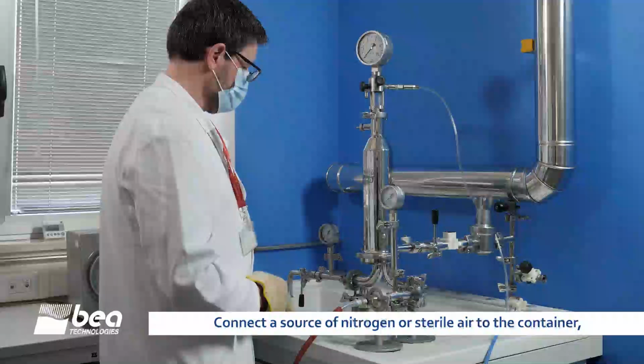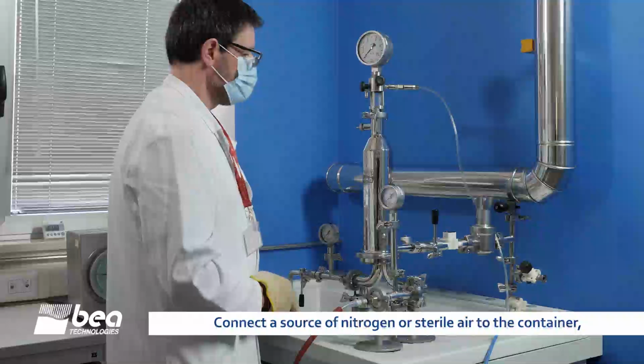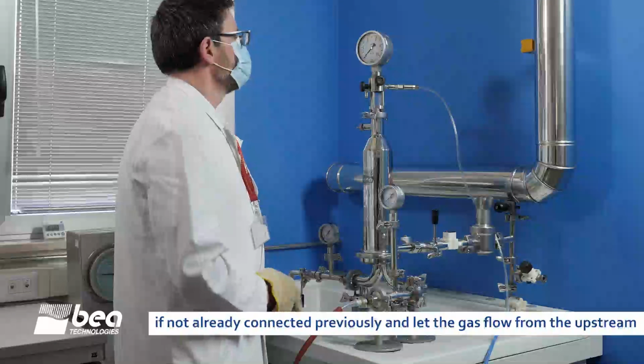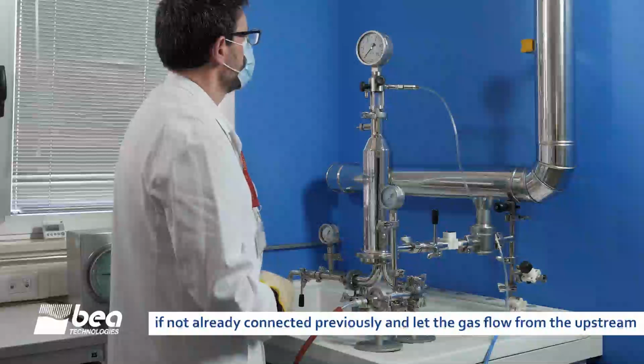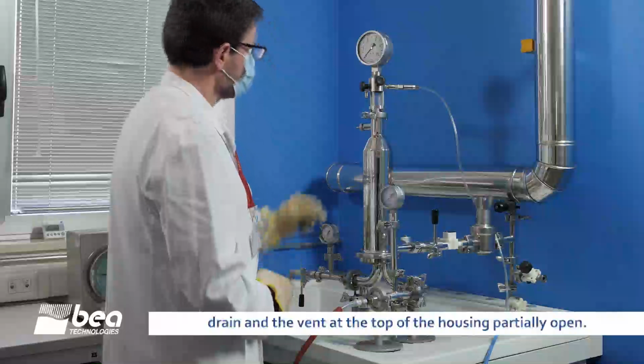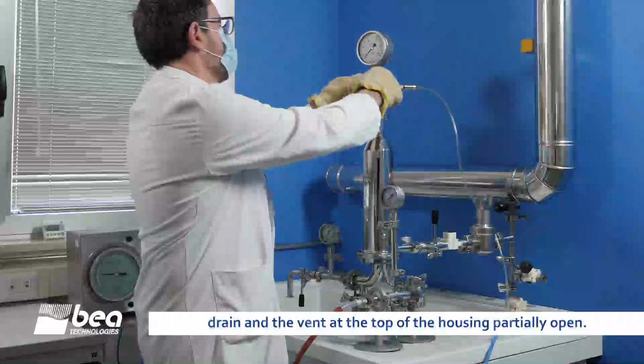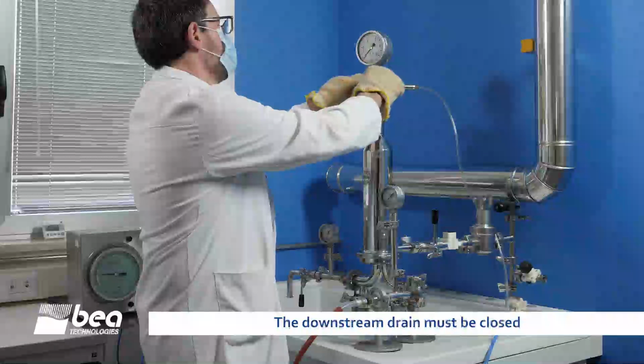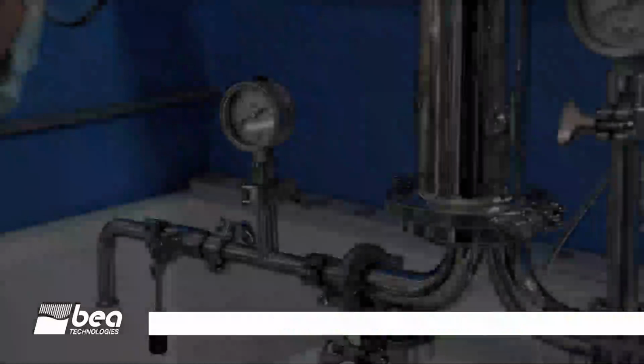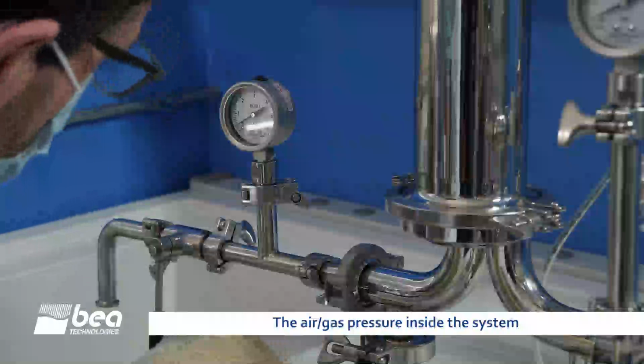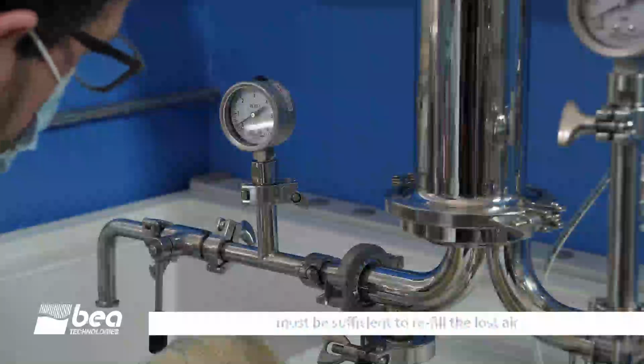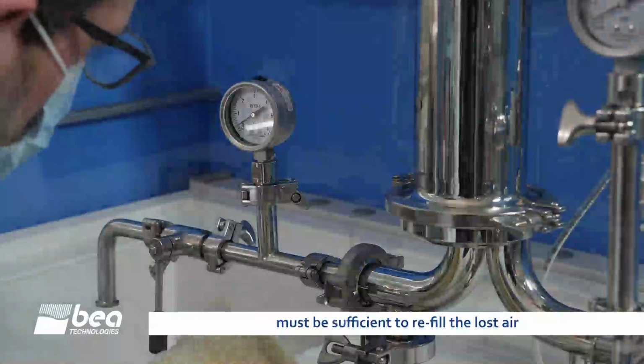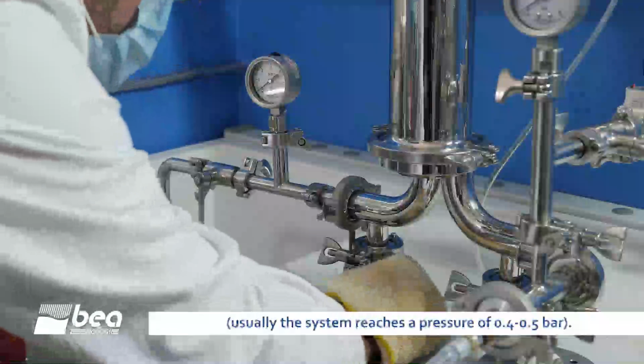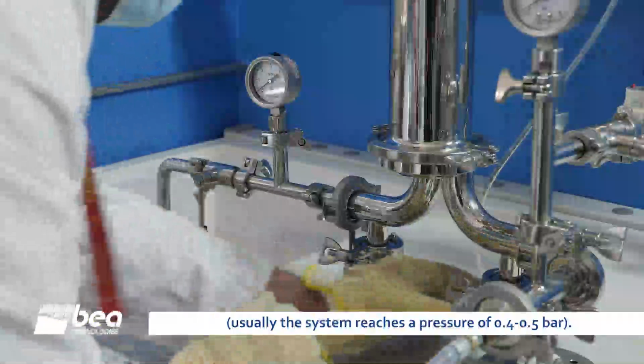Connect a source of nitrogen or sterile air to the container if not already connected previously, and let the gas flow from the upstream drain and the vent at the top of the housing partially open. The downstream drain must be closed. The air-gas pressure inside the system must be sufficient to refill the lost air. Usually the system reaches a pressure of 0.4 to 0.5 bar.